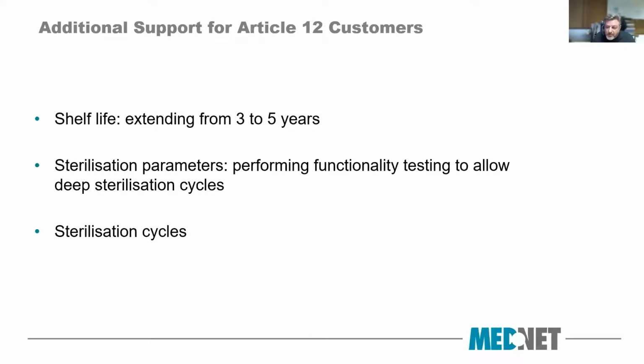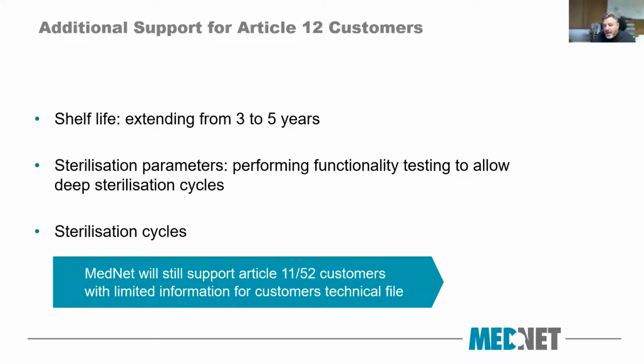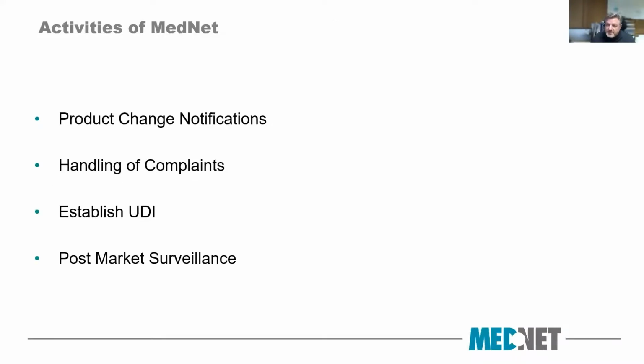We're also performing functionality testing on products that have been subjected to deep sterilization cycle parameters. These parameters are often used in the sterilization of dense packs. And as mentioned earlier, we are extending the validations for up to 3 sterilization cycles. We will continue to support customers working to Article 11 or Article 52 though.